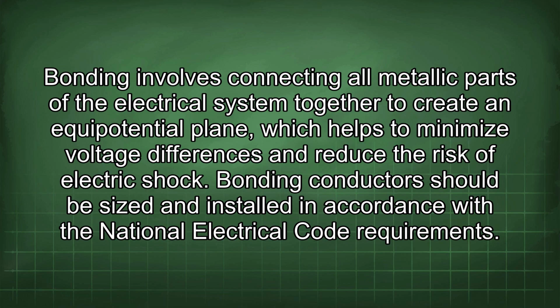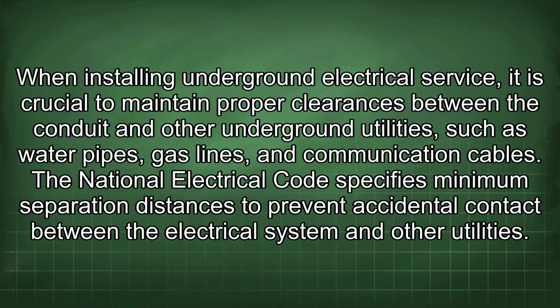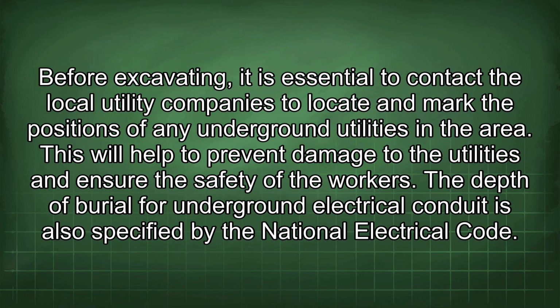Bonding involves connecting all metallic parts of the electrical system together to create an equipotential plane, which helps to minimize voltage differences and reduce the risk of electric shock. Bonding conductors should be sized and installed in accordance with the National Electrical Code requirements. When installing underground electrical service, it is crucial to maintain proper clearances between the conduit and other underground utilities, such as water pipes, gas lines, and communication cables. The National Electrical Code specifies minimum separation distances to prevent accidental contact between the electrical system and other utilities. Before excavating, it is essential to contact the local utility companies to locate and mark the positions of any underground utilities in the area. This will help to prevent damage to the utilities and ensure the safety of the workers.